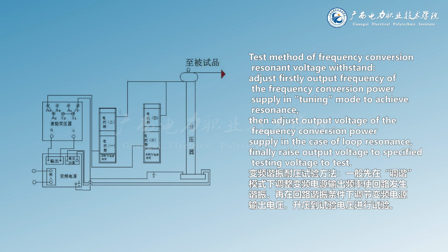Test method of frequency conversion resonant voltage withstand: first adjust the output frequency of the frequency conversion power supply in tuning mode to achieve resonance, then adjust the output voltage of the frequency conversion power supply in the case of loop resonance, and finally raise the output voltage to the specified testing voltage to test.